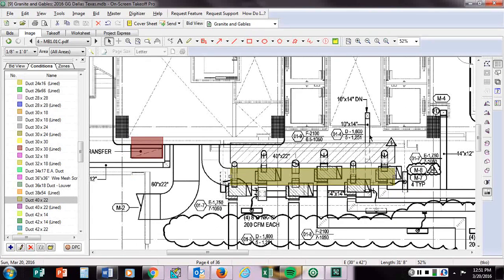This went on the other print here, and you can see this comes from this VAV box right here. You can see we've got our 2-foot connector and our other duct connector on this side. It doesn't tell us what size duct, but I think 16 by 12 might work based on the CFM. There's a register here, and then ductwork that goes down. I believe the thermostat for this box was actually on the other floor also.